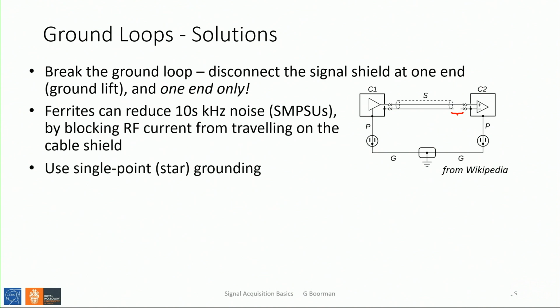Single point grounding, star grounding - don't make loops. The only connection to ground, depending on the equipment, you could unground that bit of equipment, make it floating. So there's physically no connection where it says P on the left - break that connection, and then you don't have any grounding there. This is what's known as star grounding, or single point grounding.